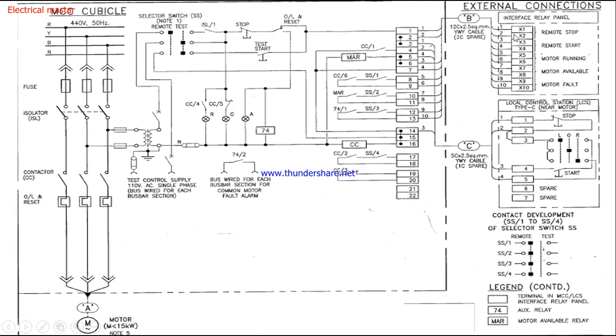From the first pin we take a 12-core 2.5 square mm cable, so 12 cables are taken out. From the cable, wire number 1 goes to the interface panel at X1, which connects to the DCS or SCADA panel stop pushbutton. The stop pushbutton NC contact output comes out at the X2 terminal. From X2, this power is taken out at pin number 2. Pins 2 and 3 are short-circuited, so whenever pin 2 receives power it is passed to pin 3.